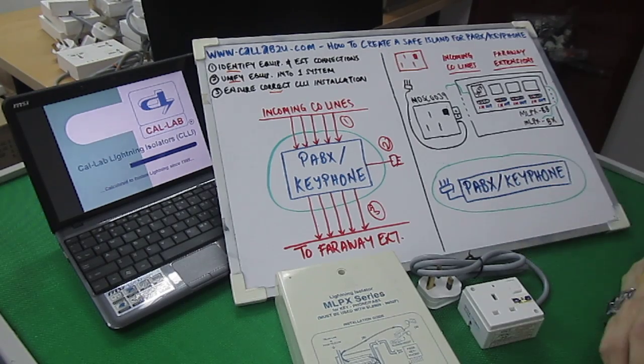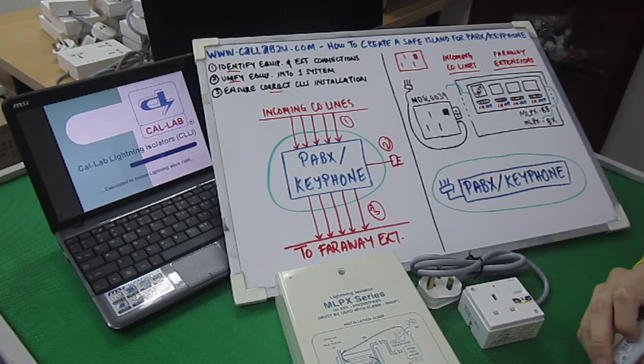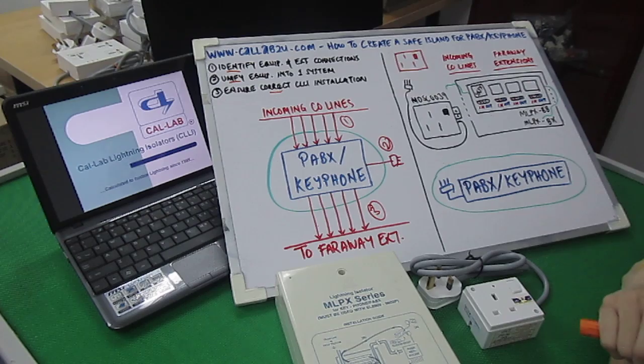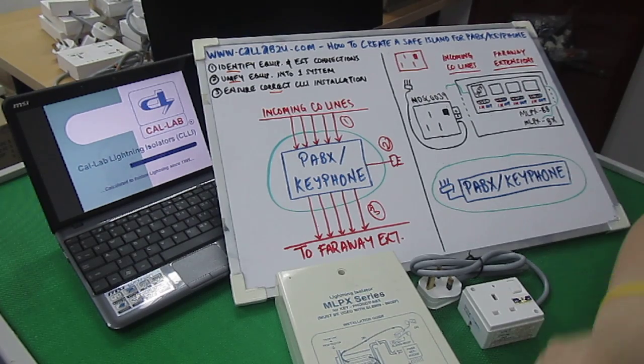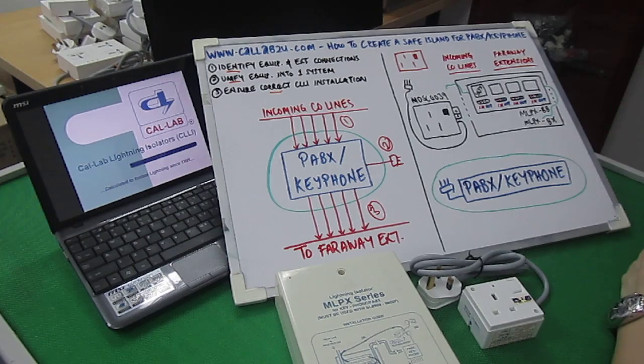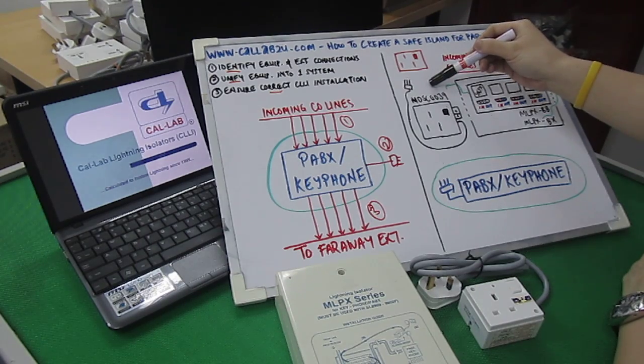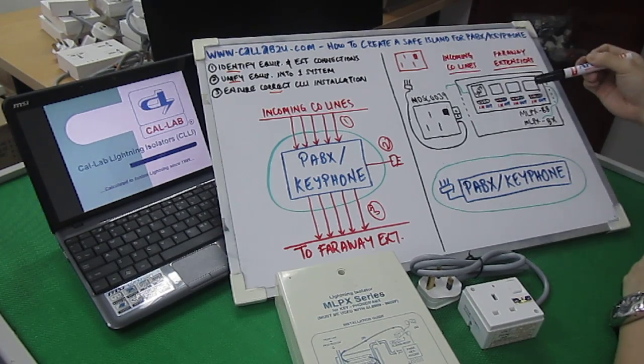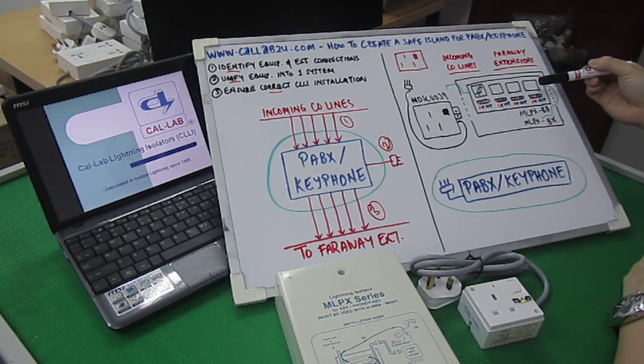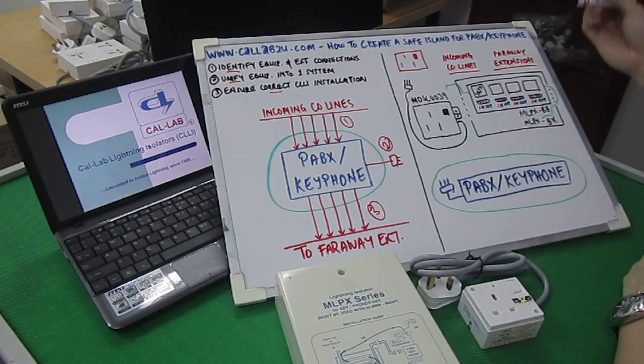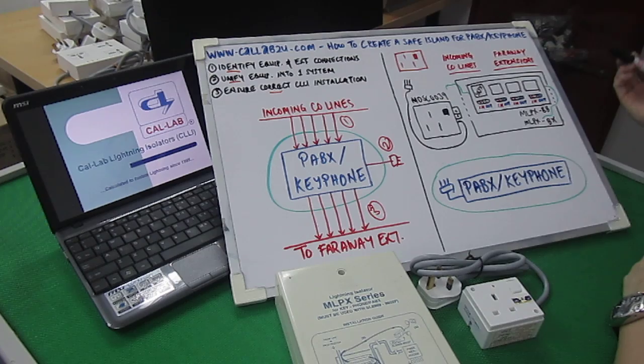Now let's take a look at step number two, which is to unify the equipment into a single system. Now, three things to note in this step. The first thing is that you need to use the correct Lightning Isolator model. In this particular case, we're using the MDSC0039 for the power supply and the MLPX series, which is for the incoming lines as well as the extension lines.